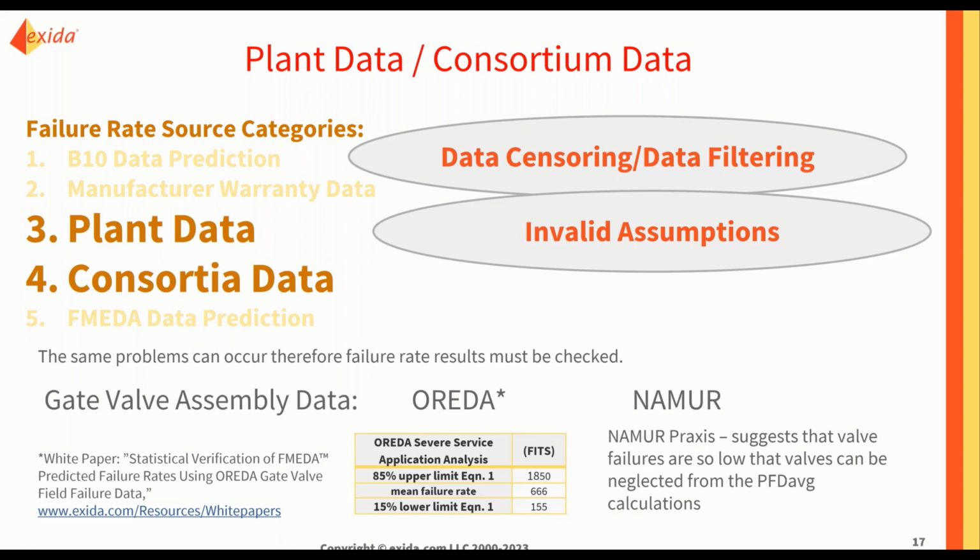And I've got a little bit of an insight into that because some of our people went and visited a number of NAMUR members and talked about how many failures they had and how many they reported. And in one case, the maintenance engineer manager said, we had 9 failures, but 7 of them were systematic, and therefore we're going to follow 61508 and we're not calling them a failure. Only 2 were real failures. Oh my goodness. Well, hold it. Were those failures where the safety function would not protect you if there was a dangerous condition? And they said, oh yes. Well, then they're real failures and you should count them. Oh no, they're systematic.